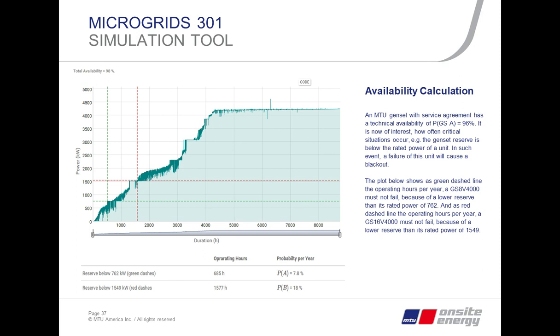In this case, we show how many hours a year, if one of the two engine models has a failure or is down for maintenance, what kind of risk is present to the customer if that engine isn't running. This simulation tool allows us to show that — maybe the customer can't abide by that percentage of risk, and they add a second engine in an N+1 arrangement to make sure they're never without power, or maybe there's a way they can manage it, and as long as they're aware of it, they can make those intelligent decisions.